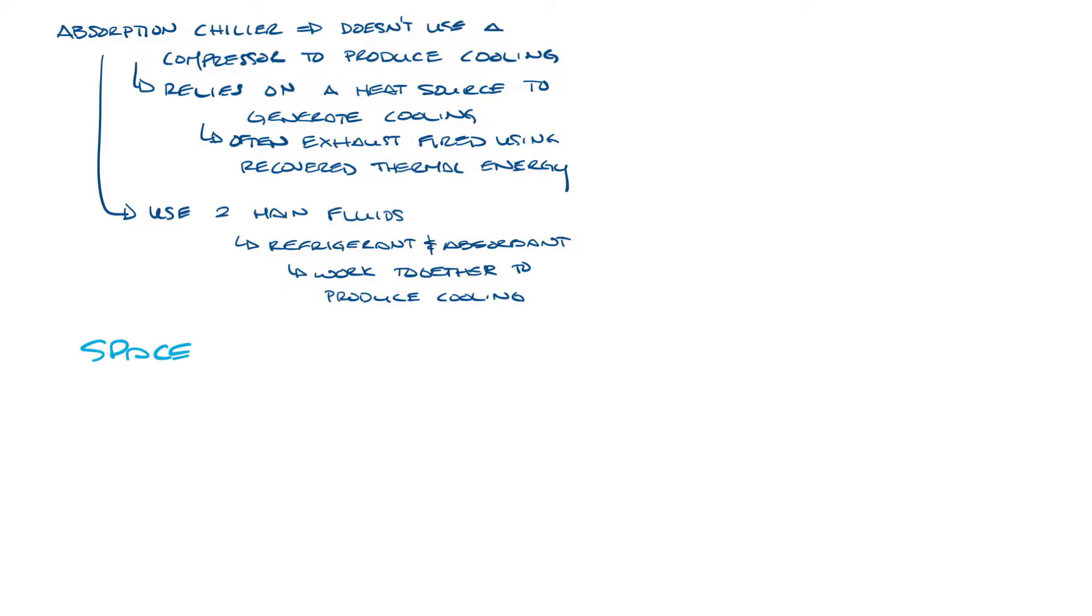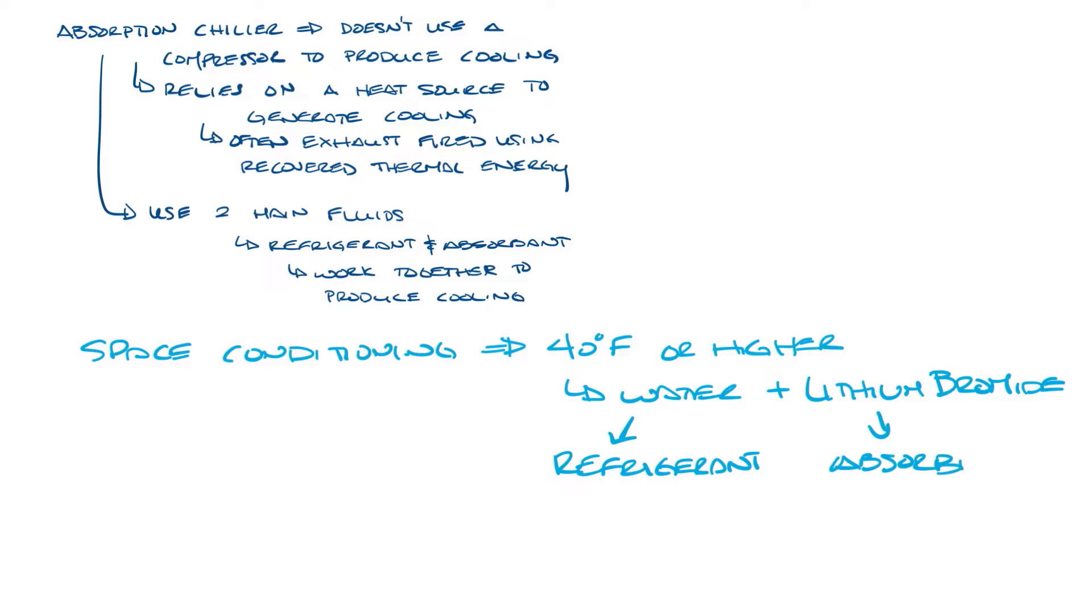For space conditioning or other requirements that require chilling fluid temperatures of 40 degrees Fahrenheit or higher, water lithium bromide is the most common solution. With water and lithium bromide, water is the refrigerant and lithium bromide is the absorbent.